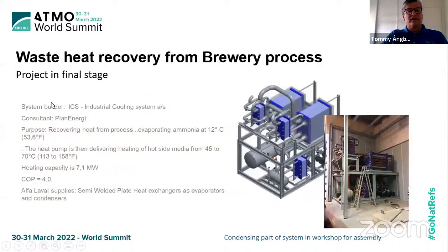Now one more, waste heat recovery from a brewery process. So here you have a process in the brewery where you can recover heat, and we do that by evaporating ammonia at 12 degrees. And then the heat pump is delivering hot water from 45 to 70 degrees. The heating capacity was 7.1 megawatt. We just take out this low value heat from the process, with a COP of 4, and we delivered evaporators and condensers into that set, and it's just now installed. But it shows how it's possible to do fossil-free heating, and it's a kind of electrification on an industrial basis as well.